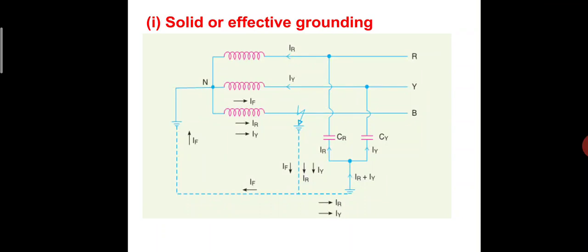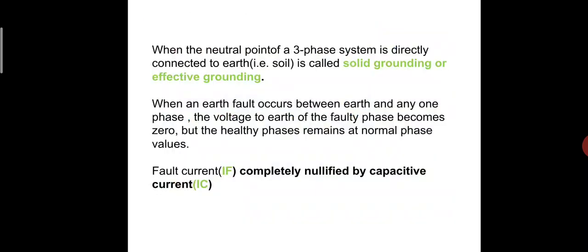First: Solid or Effective Grounding. The neutral point of a three-phase system — R, Y, B — is directly connected to earth through a wire of negligible resistance and reactance. This is called solid grounding or effective grounding. When an earth fault occurs between earth and any one phase, the voltage to earth of the fault phase becomes zero, but the healthy phases remain at normal phase values.